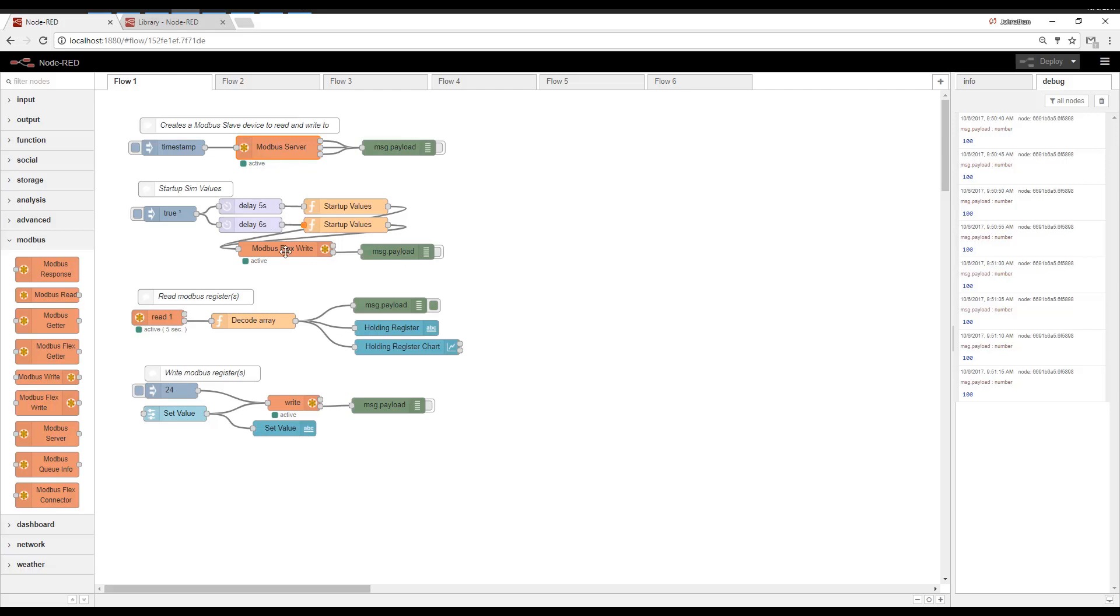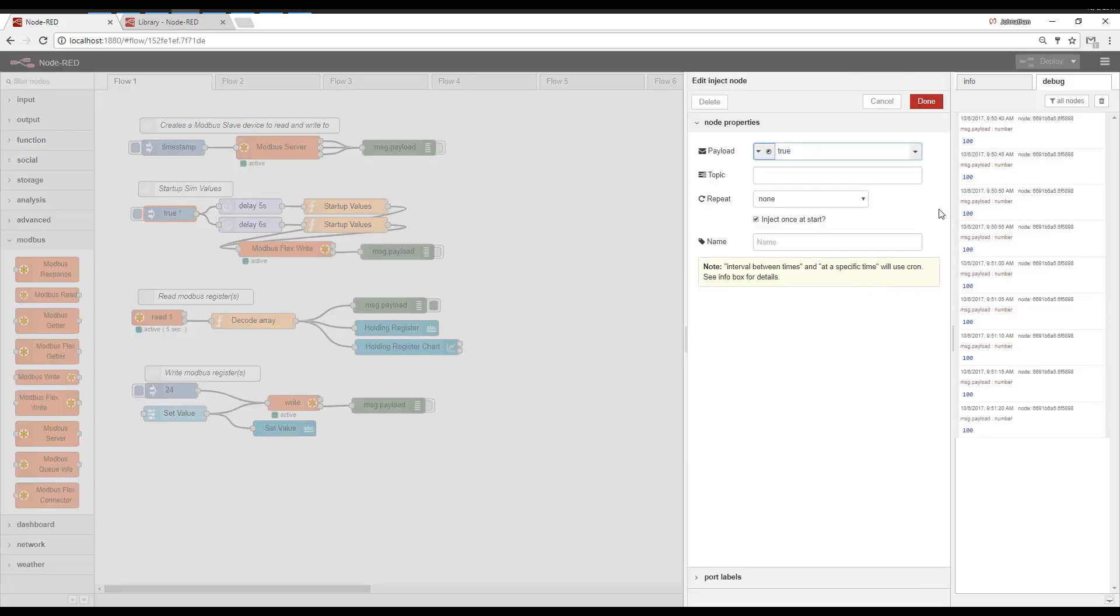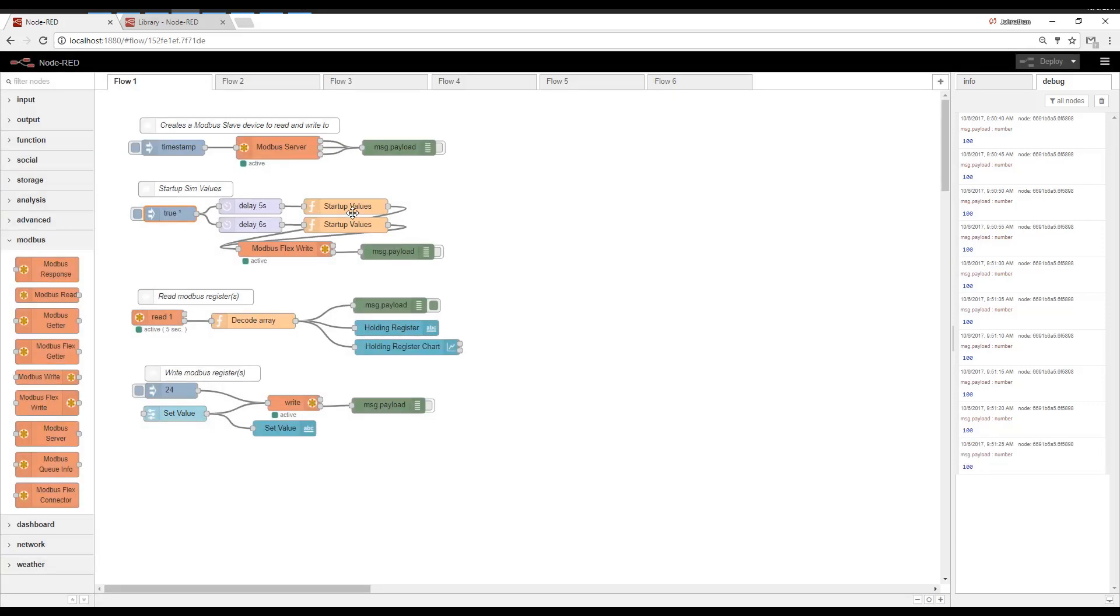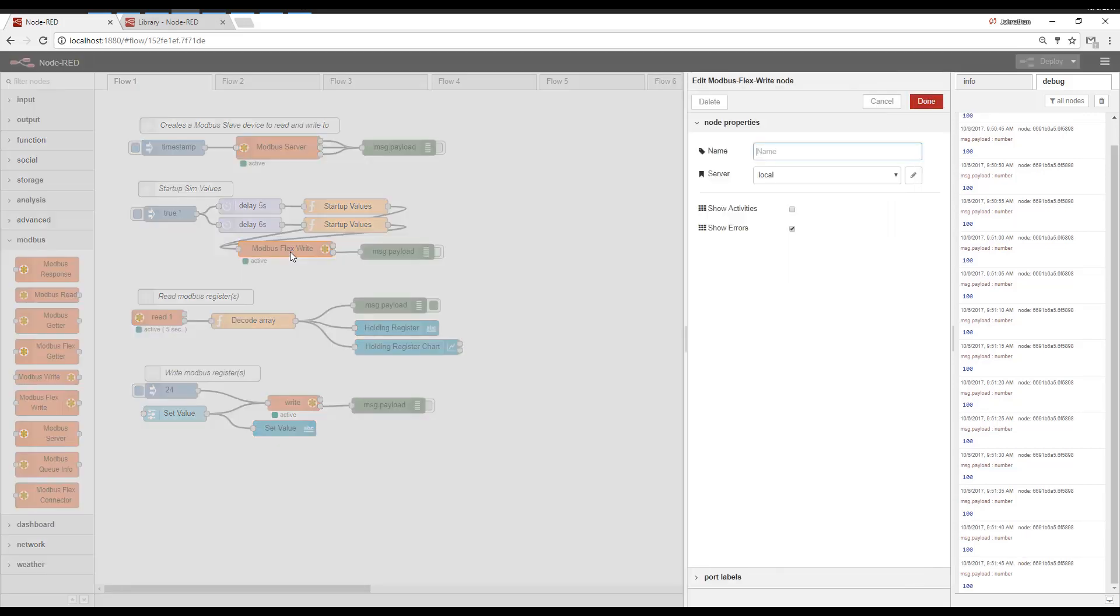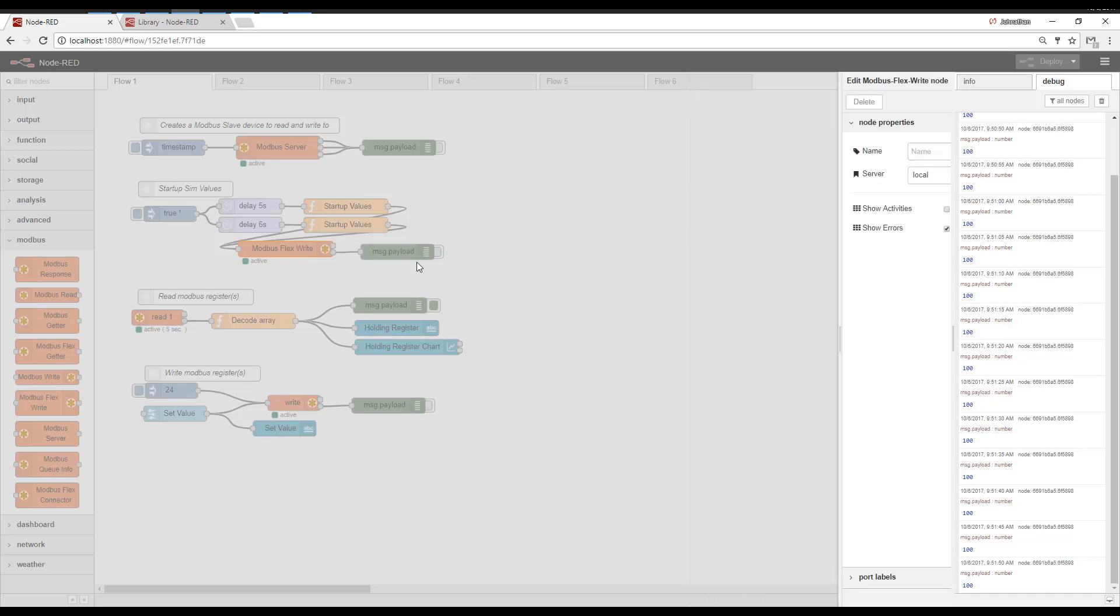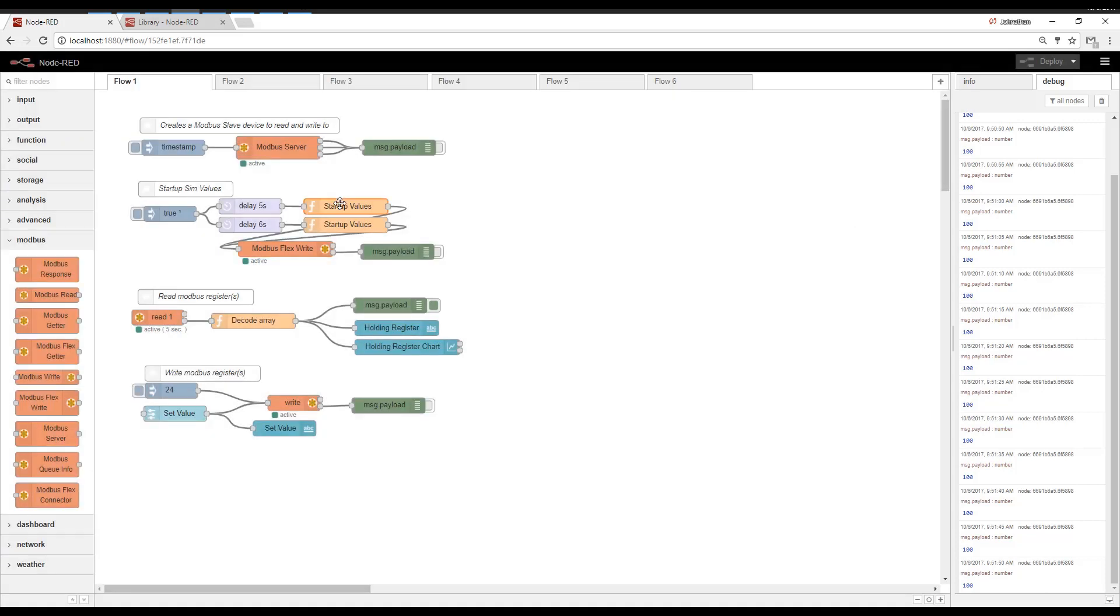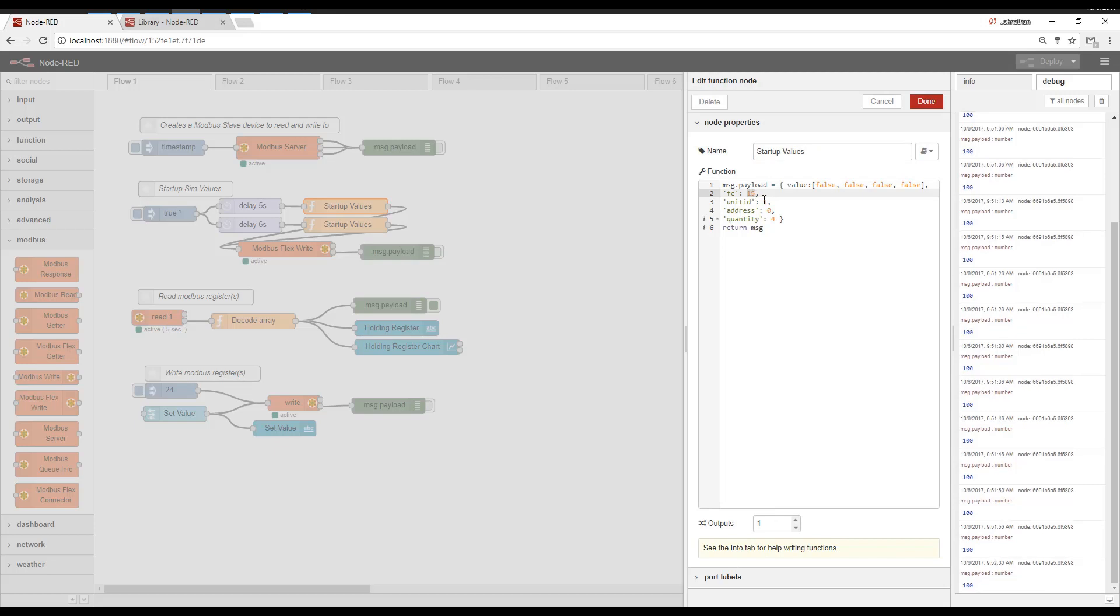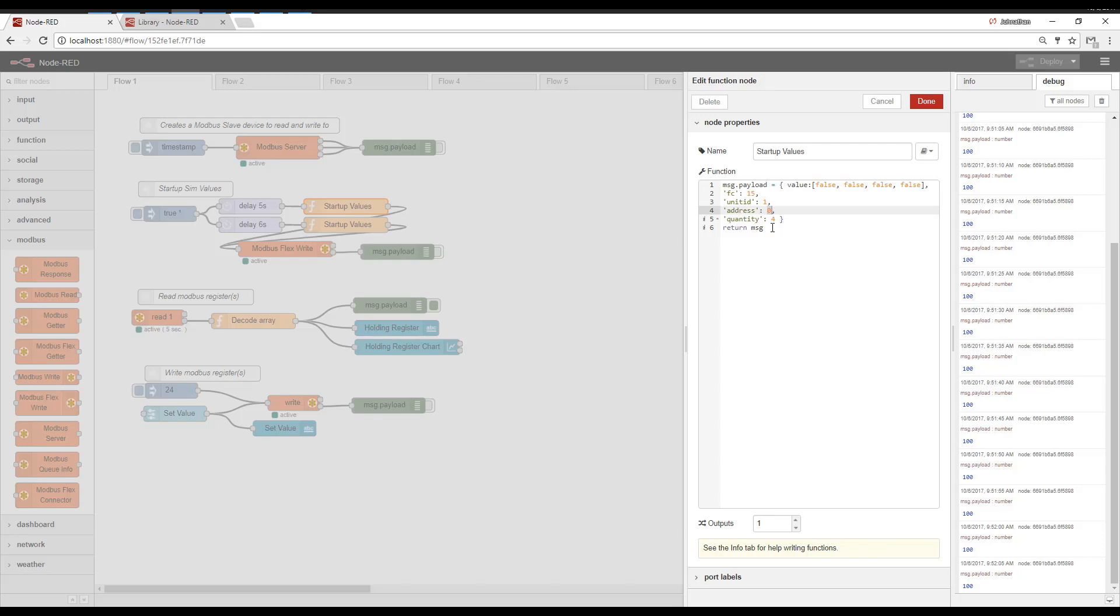So this is a little example where whenever we start up, we're going to inject once on startup. And here's a couple of delays and we're going to use these functions and a Modbus Flex Writer. The Modbus Flex Writer is valuable because you can write to any different type of register. There's no configuration in it. You just send it what you want to write in the message object. So let's look at a couple of these. This one says we're going to do a function code 15, which is going to write multiple coils. We're looking for the Modbus slave device address one. We're going to start at register zero and we're going to write four. And here are the values. We're going to set them all false.